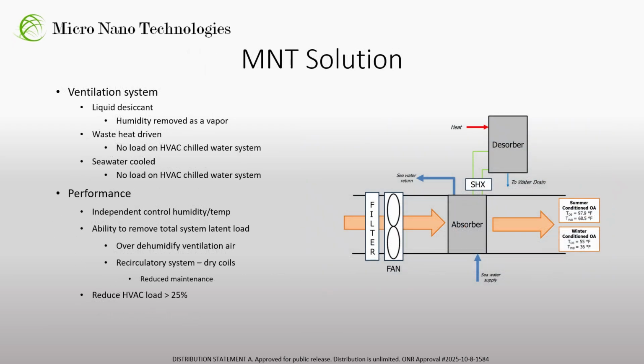A liquid desiccant ventilation system based on MNT's technology is being scaled to address the Navy's requirements. This system will remove water directly from the ventilation air as a vapor, eliminating the need to subcool the air to remove moisture by condensation. The liquid desiccant will be regenerated using waste heat, with the system being cooled using seawater. This removes the entire ventilation system load from the ship's HVAC chilled water system. Additionally, the use of an intercooled absorber provides the ability to independently control the exit air humidity and temperature conditions, increasing system functionality and flexibility.